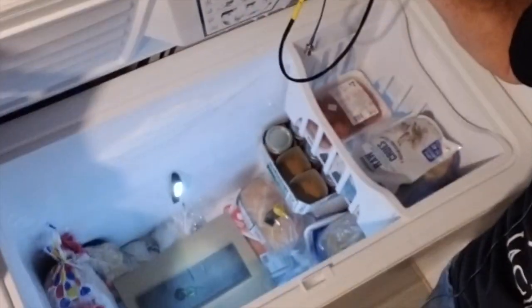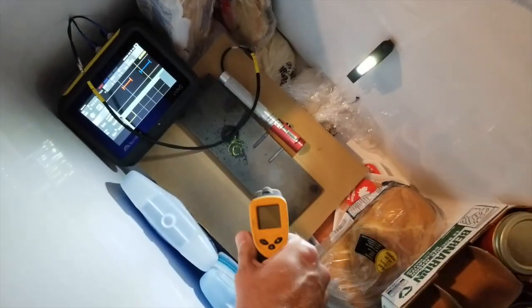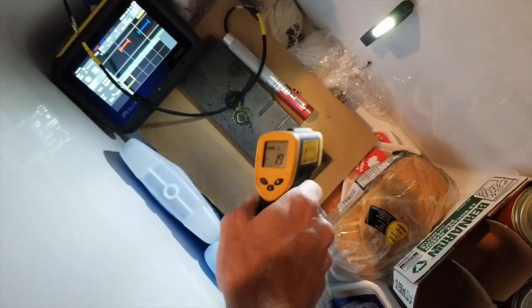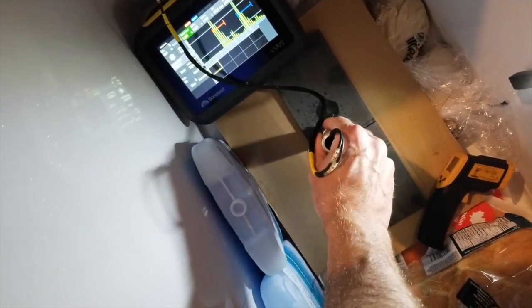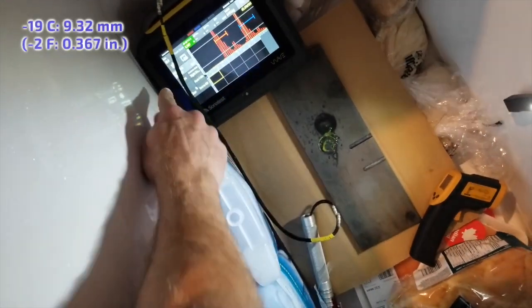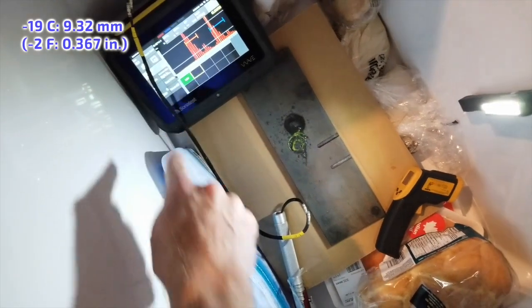Now, those temperatures are not going to be an issue for us today, at least when we get started, because what I did last night in order to try and maximize the effect of what we're going to do is I took a 3/8 inch piece of steel, which is 9.5 millimeters, and I put it in the freezer. We'll check the temperature of the plate to start. What we get is about -19 Celsius. Using half-wave rectified signal, echo to echo on the first peak, we get 0.367. I'll store that on the data logger, and we'll go out to the barbecue.